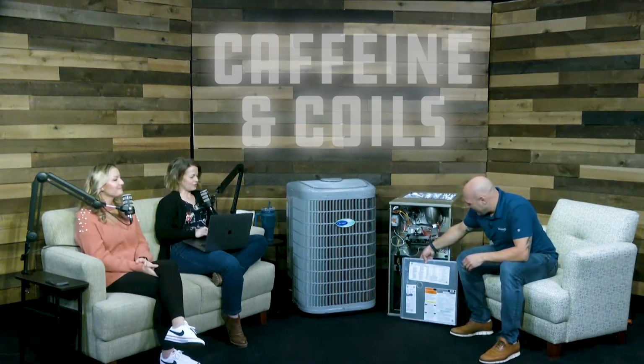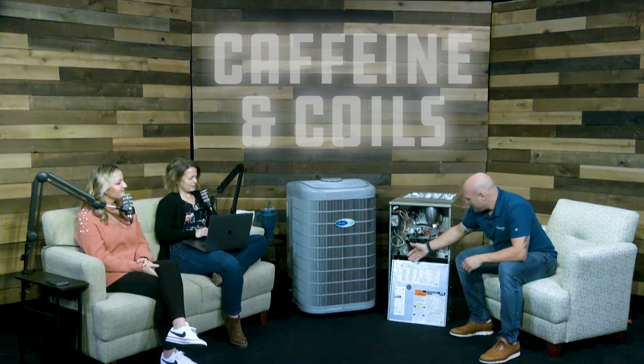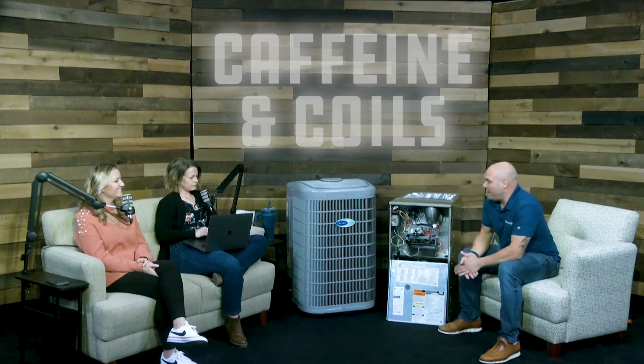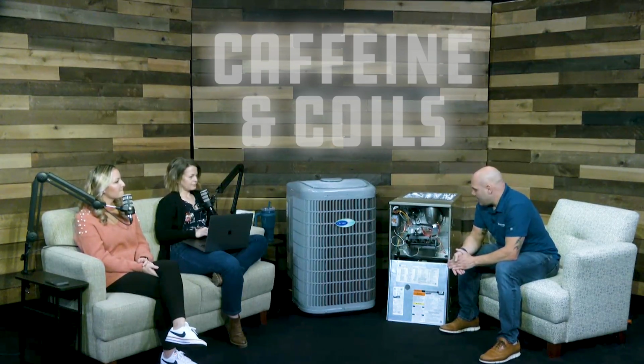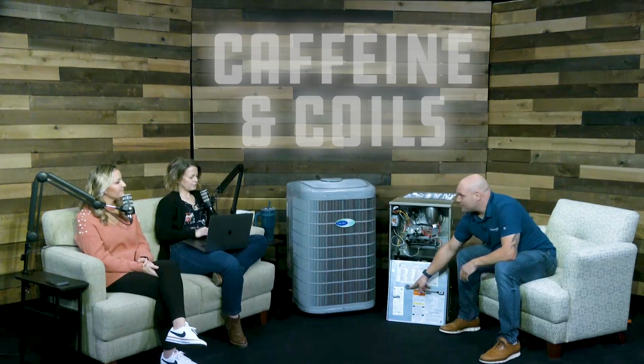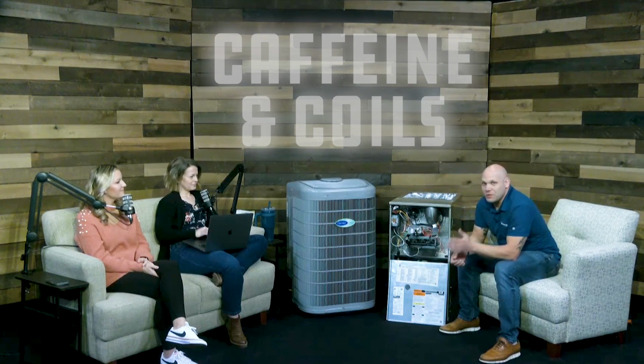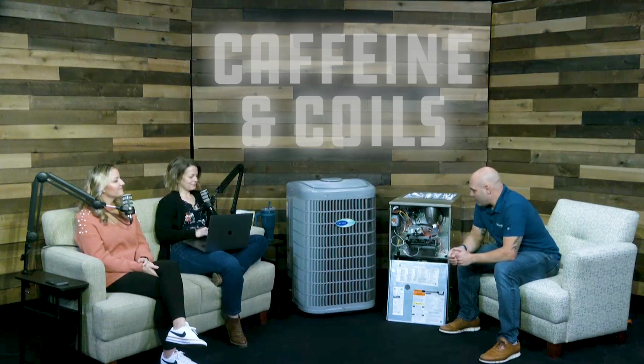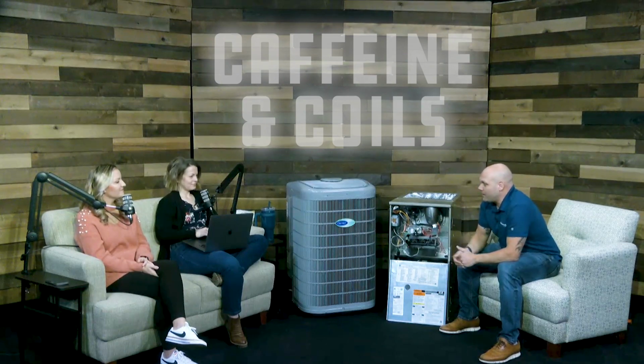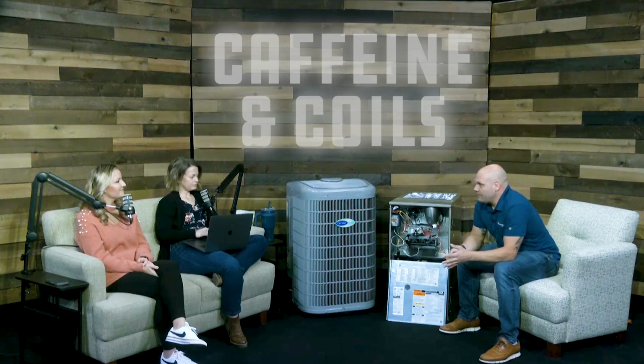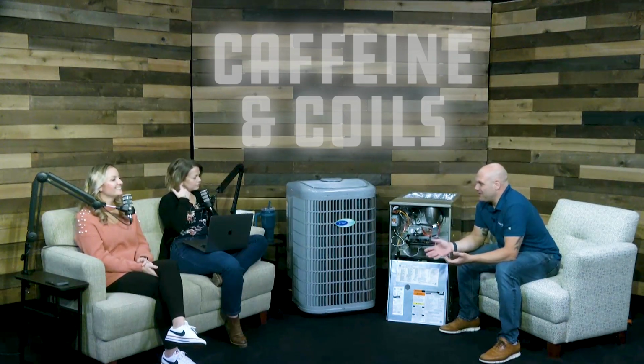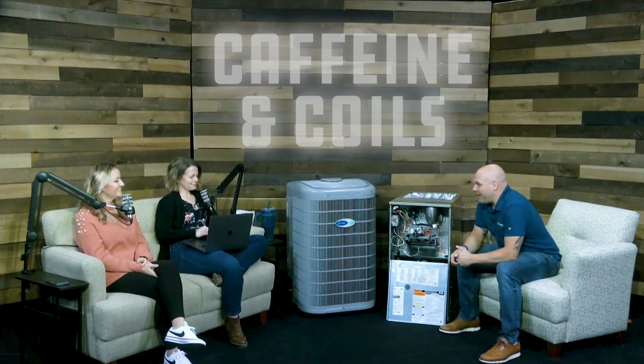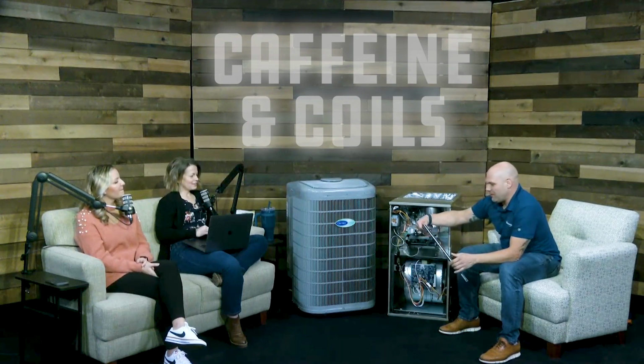All right, so on the door of the furnace, and no matter what brand you're working on, obviously we'd love for you to work on Carrier Bryant, but every brand will have this same setup. You have a rapid flash that you'll see here, and you have a slow flash. The rapid flash is your first number in the error code, and your slow flash is the second number. So if you have an error code 33, which is what we're talking about, you'll have 3 rapid and then 3 slow, and that is an error code 33. Nice. And for any other error code, it works that way too. Let me see if there's another common one.